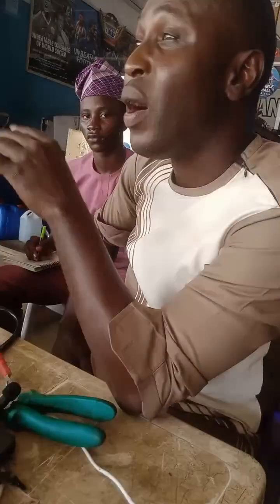Number 1: write the cable gauge for VAC and VDC for a 20 kVA, 120 VDC inverter. I will not be the one to give you the solution, you don't want me answering the assignment as I give you the question. But we should know the active energy to use. Use 20 kVA, let's assume the power factor is 0.9.